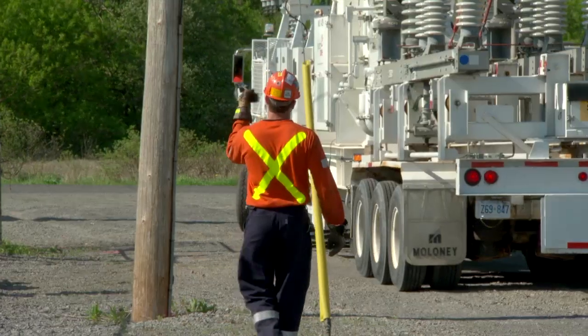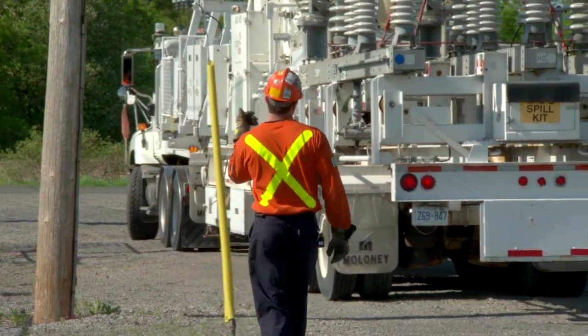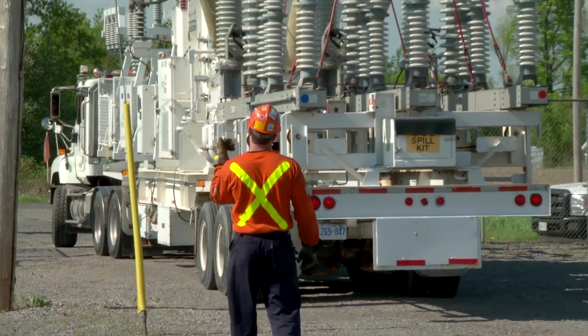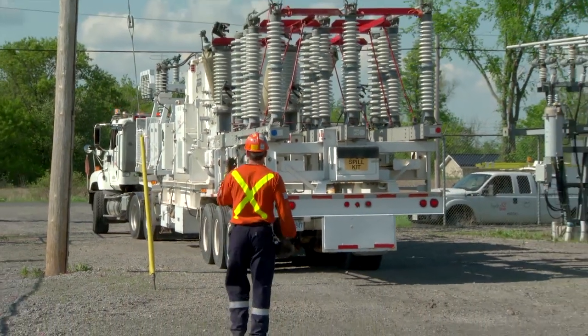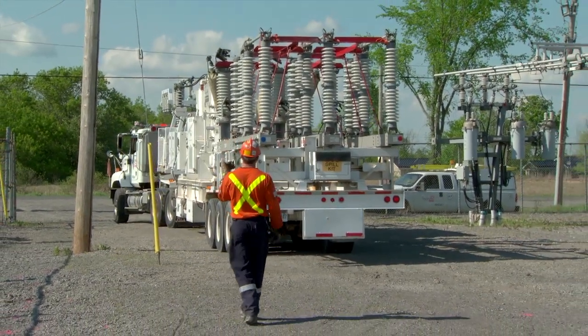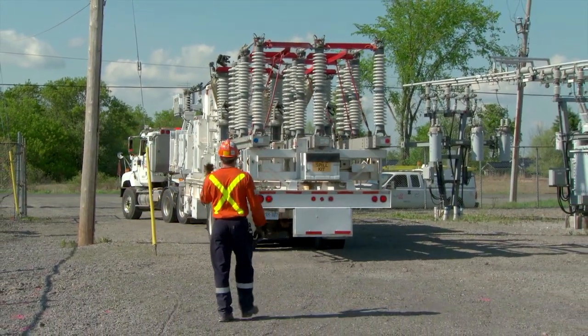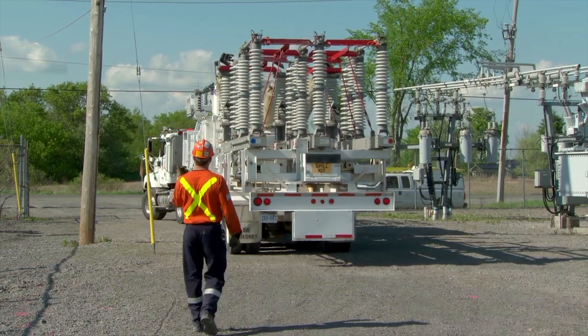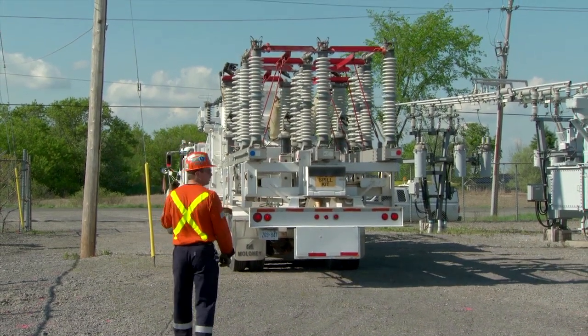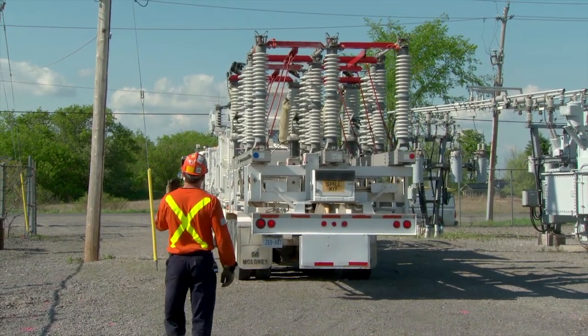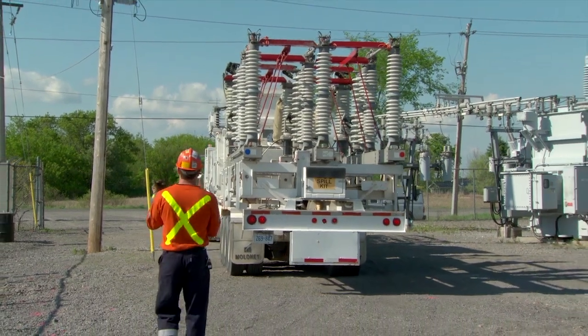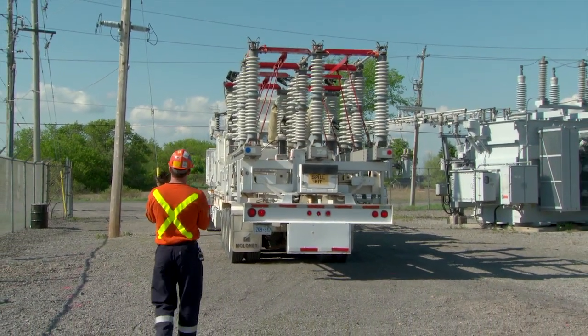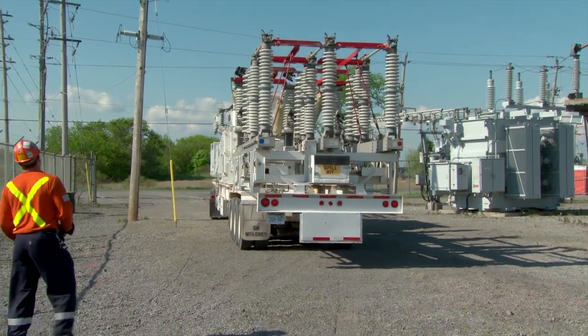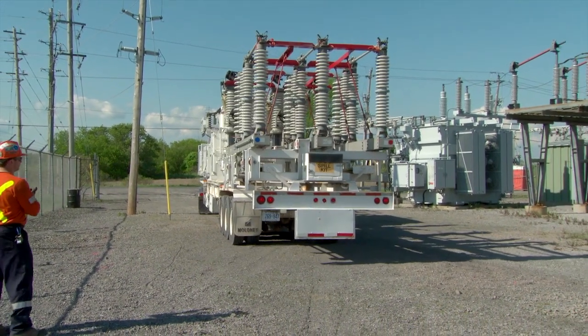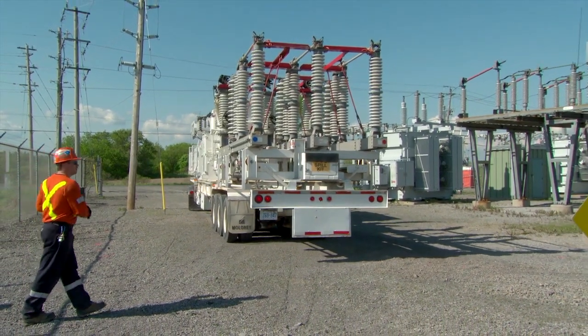On 115 kV mobiles, if the fence is located on the red phase side of the MUS, an additional 1.5 meters is required between the fence and the mobile because the red phase on the high voltage fuse swings outward. This means a total required clearance of 4.5 meters. The MUS should also be parked as far back as possible, leaving gate access to the station for trucks, cranes, floats, and other required equipment.